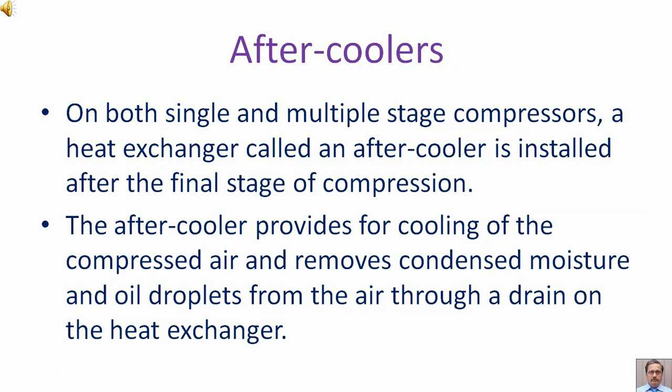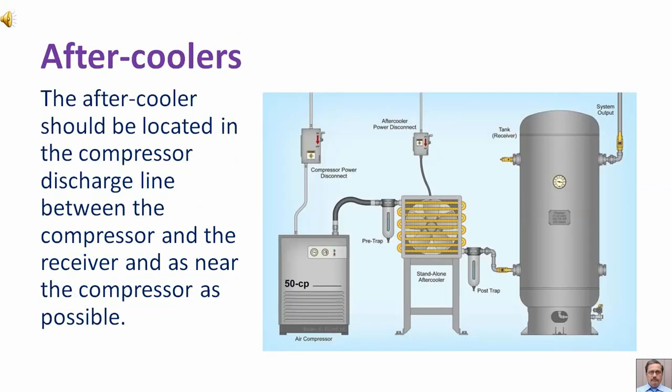On both single and multiple stage compressors, a heat exchanger called an aftercooler is installed after the final stage of compression. The aftercooler provides for cooling of the compressed air and removes condensed moisture and oil droplets from the air through a drain on the heat exchanger. The aftercooler should be located in the compressor discharge line between the compressor and the receiver, and as near the compressor as possible.